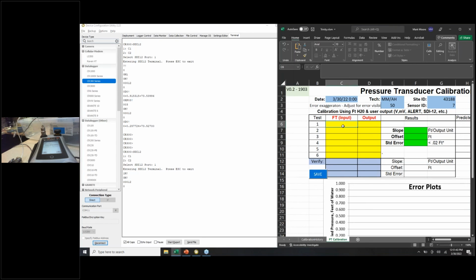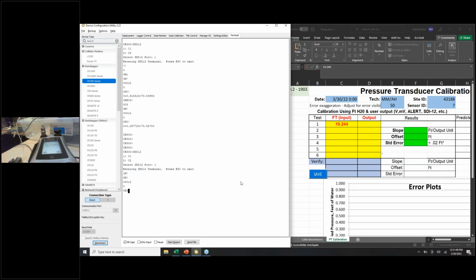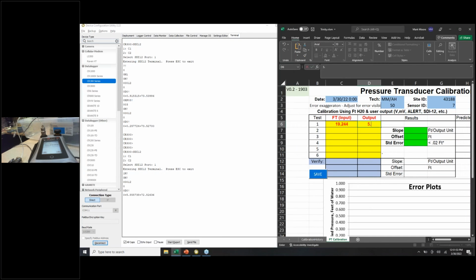And at the time, that calibrator was reading 19.244. To get the data from it, the output was 5.8557. You know, all right, that's a little strange. We would expect it to be close to 19 feet. It's an SDI12 PT, but we're only getting 5.85 something. Well, let's keep calibrating. Let's see what we get.